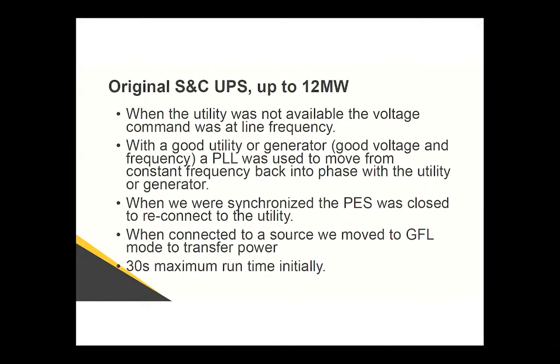All of these systems had generators because we had a very limited runtime. And so when a generator would start, or if the utility would come back, we would synchronize to it because we had voltage measurements on both sides of our power electronic switch. So we could resynchronize and transfer back. One of our concerns was when we transfer back to the utility or to a generator, how do we keep control of power? And so what we did was when we transferred back, we go to a grid following mode so that if our angle was a little bit off, we still had control of power.